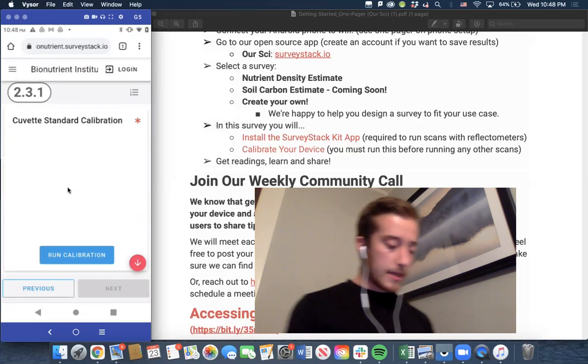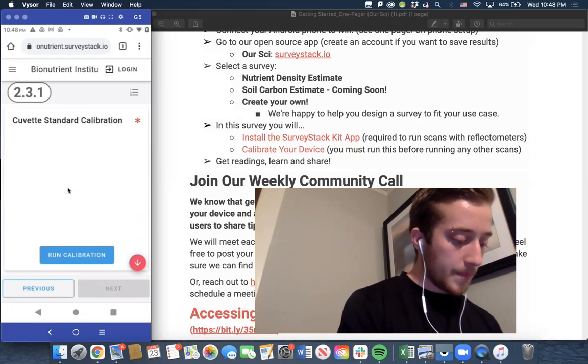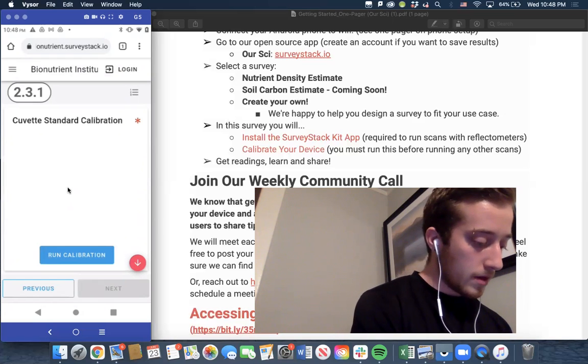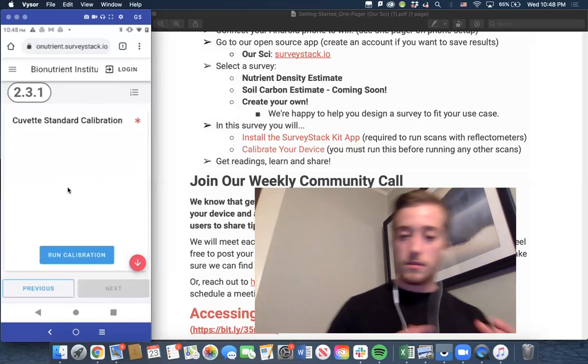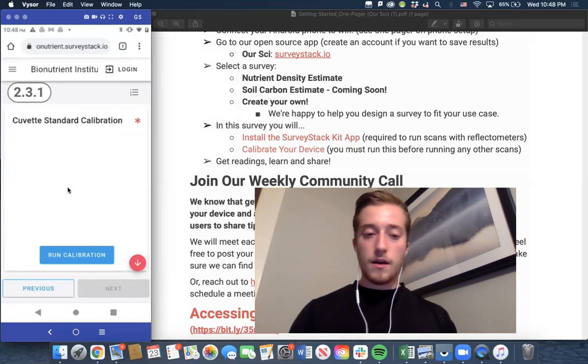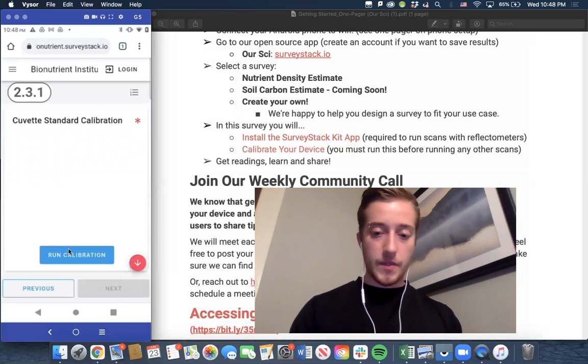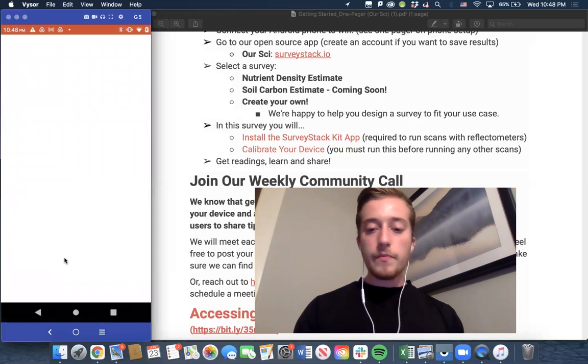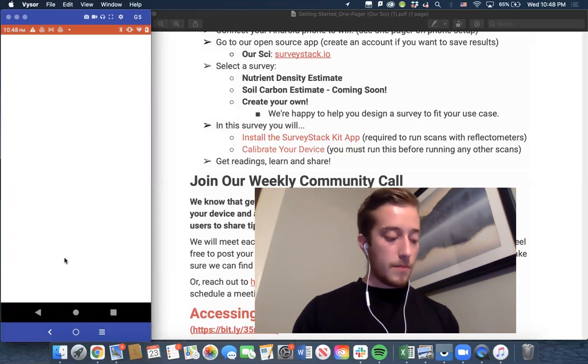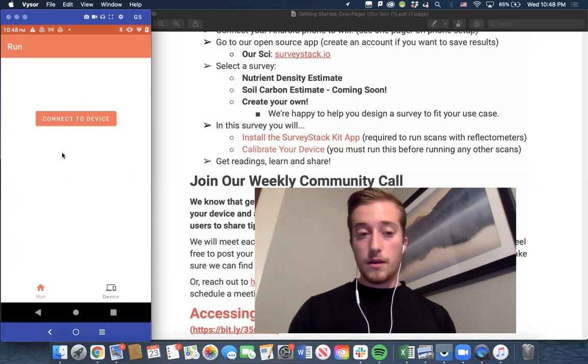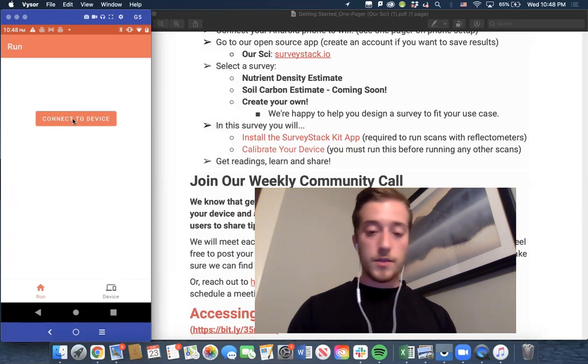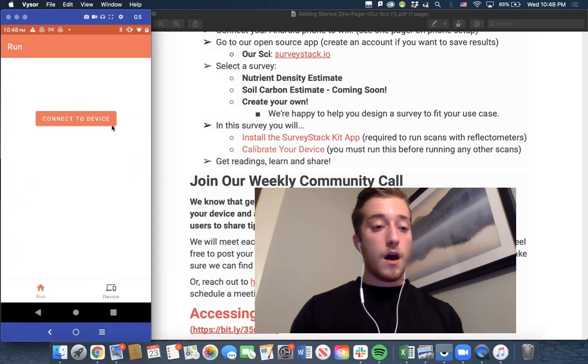Once this is set up though, my cuvette standard is clean, it's inserted, the clamp is right, the positioning is correct. I'm gonna set this on a table, a space that is stable. Even your hands' motion can cause some inconsistency. So set it on a stable surface, and you can run your calibration. And again, just like with the open standard, you will see the LEDs, but obviously the clamp is closed and the standard is in place, so it will be less obvious.